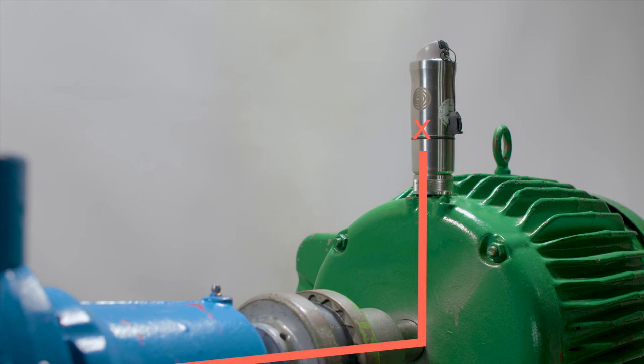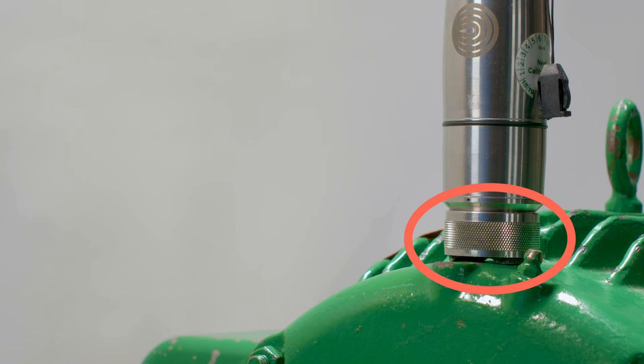It is important to ensure the X on the sensor is in line with the shaft and the sensor is stable on the machine surface. If necessary, the magnet attached to the sensor can be adjusted to land more snugly on the rounded surfaces.